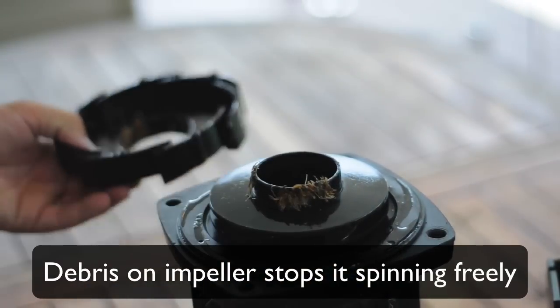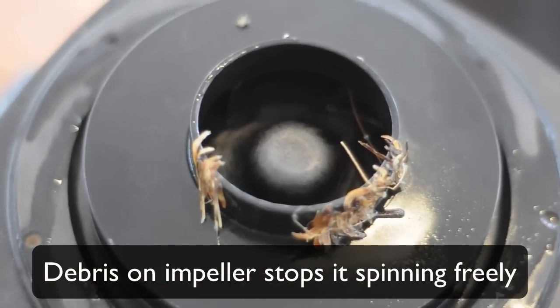Now, what we're left with is the debris on the impeller. This is what's stopping the impeller from spinning freely and making that humming noise.